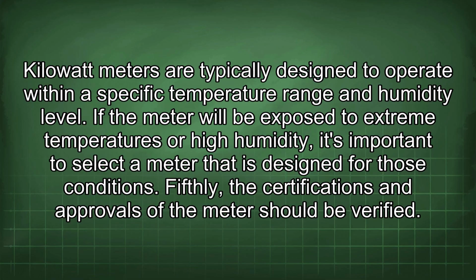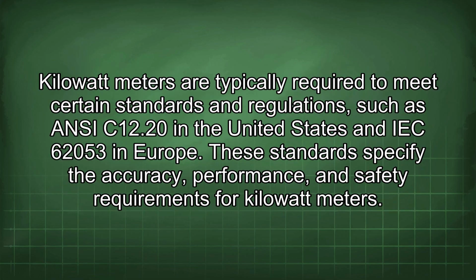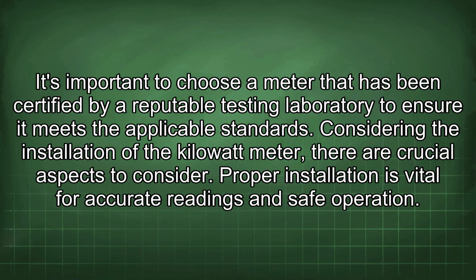Fifthly, the certifications and approvals of the meter should be verified. Kilowatt meters are typically required to meet certain standards and regulations, such as ANSI C12.20 in the United States and IEC 62053 in Europe. These standards specify the accuracy, performance, and safety requirements for kilowatt meters. It's important to choose a meter that has been certified by a reputable testing laboratory to ensure it meets the applicable standards.